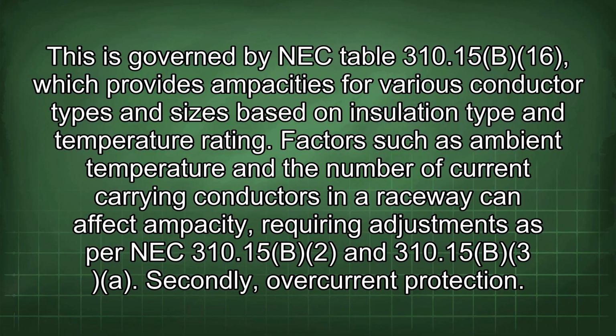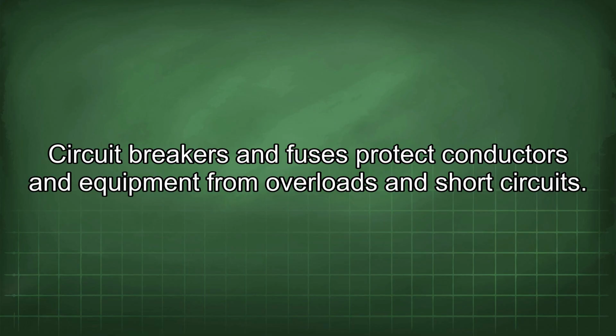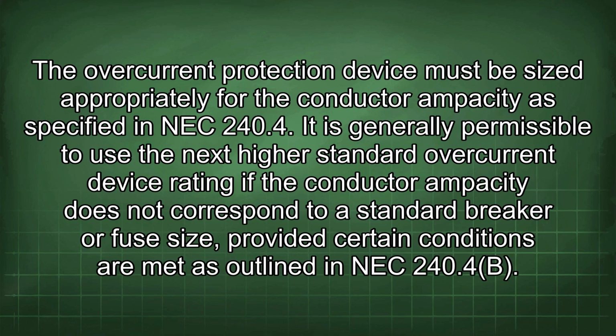310.15(B)(3). Secondly, overcurrent protection. Circuit breakers and fuses protect conductors and equipment from overloads and short circuits. The overcurrent protection device must be sized appropriately for the conductor ampacities specified in NEC 240.4. It is generally permissible to use the next highest standard overcurrent device rating if the conductor ampacity does not correspond to a standard breaker or fuse size, provided certain conditions are met as outlined in NEC 240.4(B).